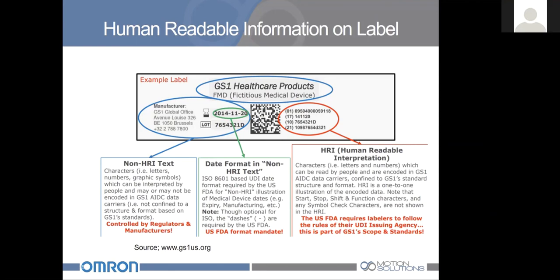There's not a minimum font size for human readable information that's specified by the FDA or GS1. However, the FDA, through their labeling standards, 21 CFR 801.15, state that text must be prominent. So although that's somewhat of a gray area statement, in an audit or other situation where there is a complaint about unreadable text, the FDA could fall back upon that regulation if the font becomes too small to be easily legible.